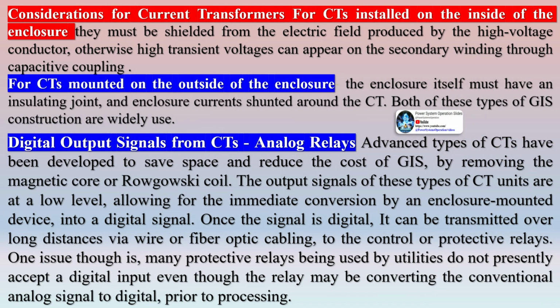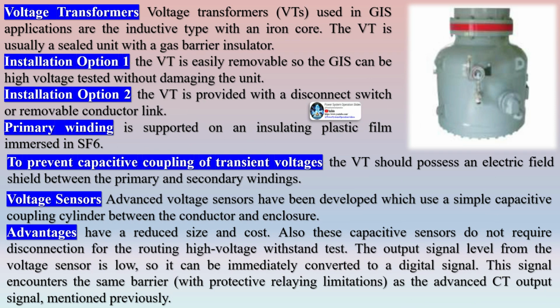Considerations for current transformers. CTs installed on the inside of the enclosure must be shielded from the electric field produced by the high voltage conductor, otherwise high transient voltages can appear on the secondary winding through capacitive coupling. CTs mounted on the outside of the enclosure itself must have an insulating joint, and enclosure current shunted around the CT. Both of these types of GIS construction are widely used.